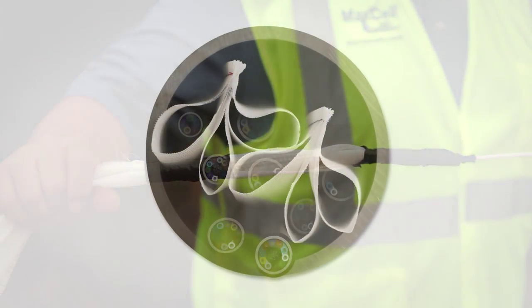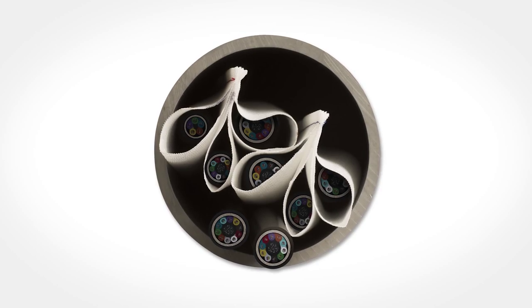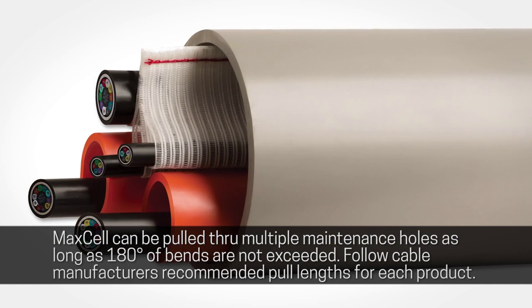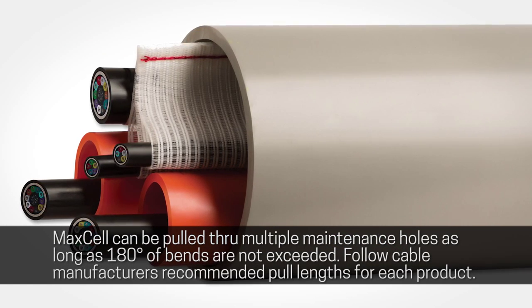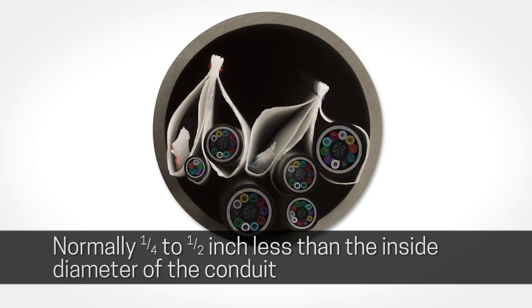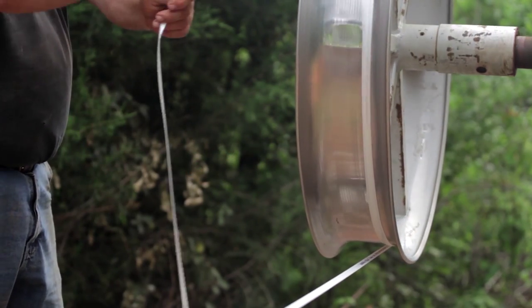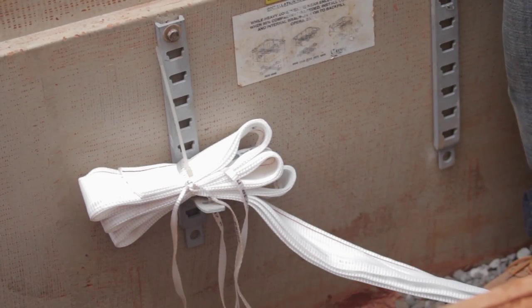When pulling in MaxCell, designers should make every effort to conform to industry standards with regard to distances between any two pull points, number of bends between any two pull points, and proofing of conduit pathway using appropriately sized mandrels. Here, the pull tape is being mechanically pulled by the pulling machine or tugger.